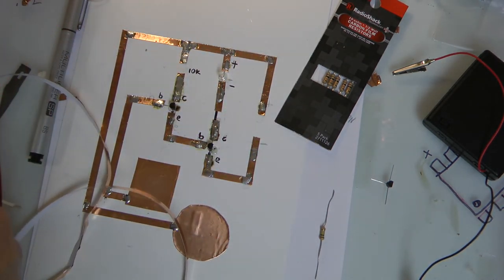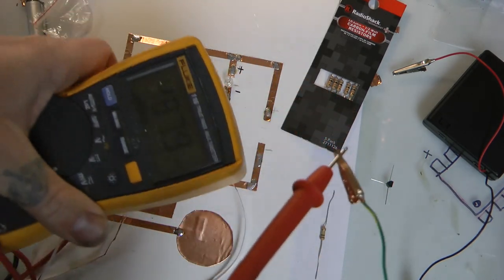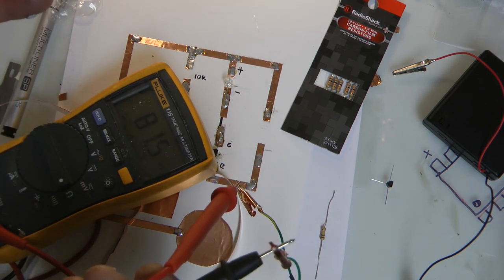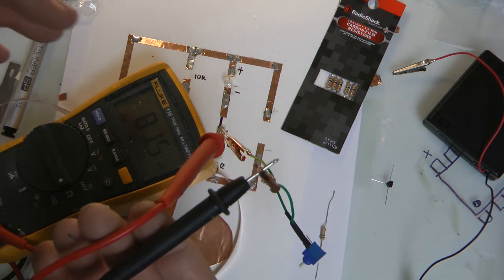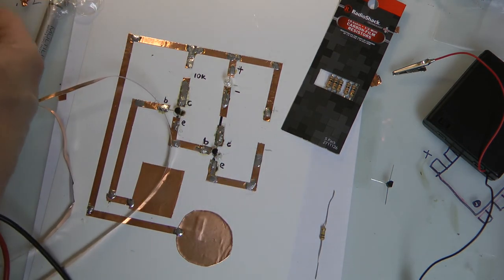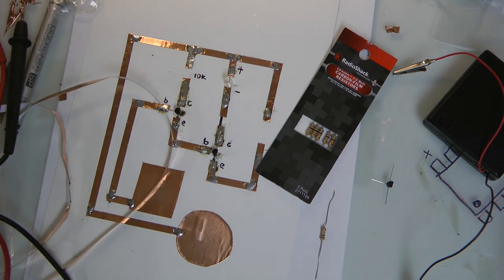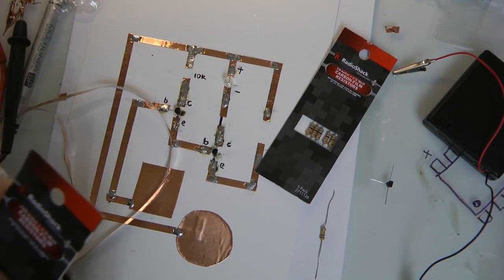And you can see how much sensitivity you want. After you're done, you can take a multimeter, put it to ohm, clamp it. And it gives you the ohm value. Now if you push it, put it down, see how it settles down. So don't hold the multimeter while you're doing this because it will pick up your value next to ground. Don't do that. So 81K. So if I use 10K, maybe that's too much. So alright, I changed my mind because that one seems to be wanting 100K. So there we go. I adjusted it earlier with the potentiometer. I like doing that.